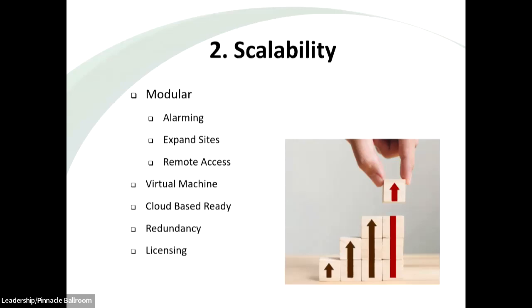Second feature, scalability. So what do we mean by that? Well, there's different types of SCADA software and adding features onto it. We call that being modular. For example, you can have a module for alarm-related functions. If your facility is manned 24/7, you may not want the module that creates alarm or enables alarm callouts. You want to make sure that if you expand sites or add sites to your SCADA system or operation, that they can be easily represented within your control system.